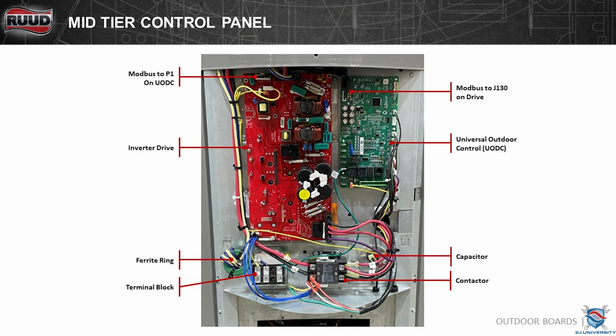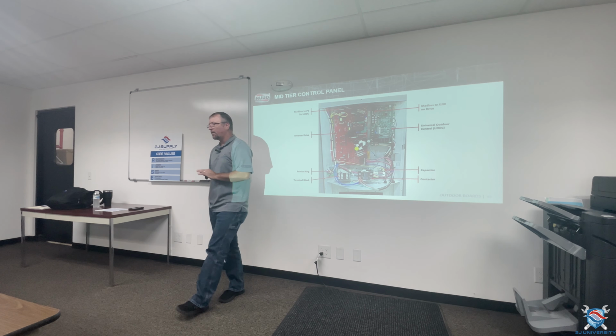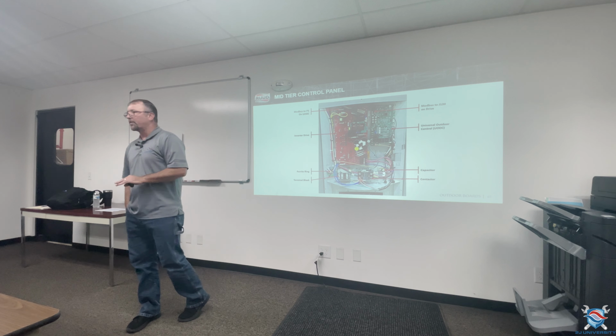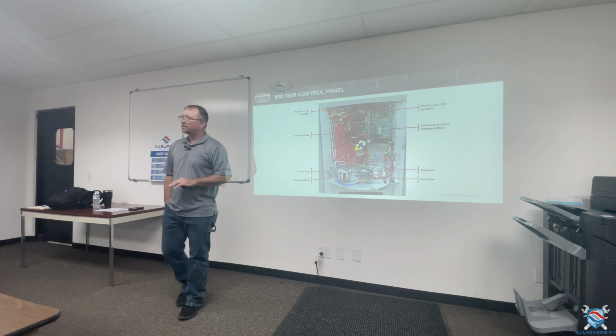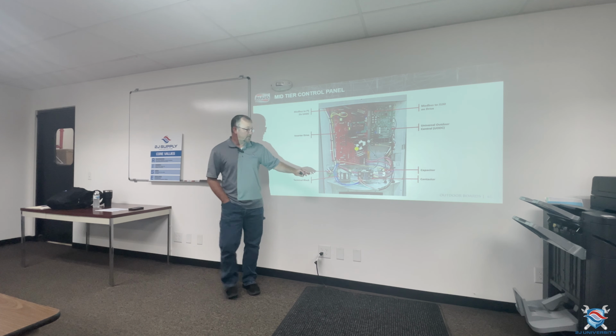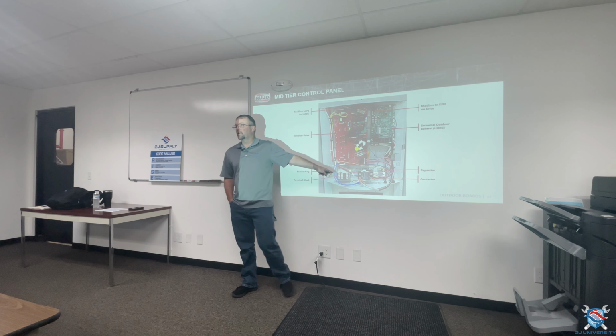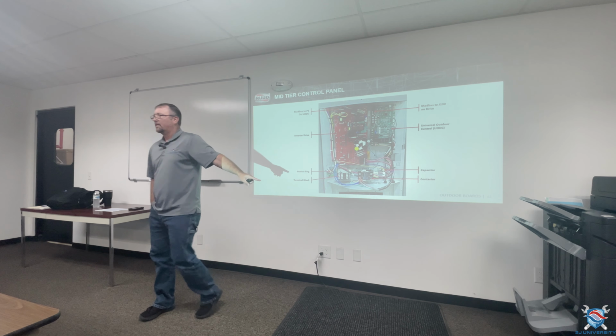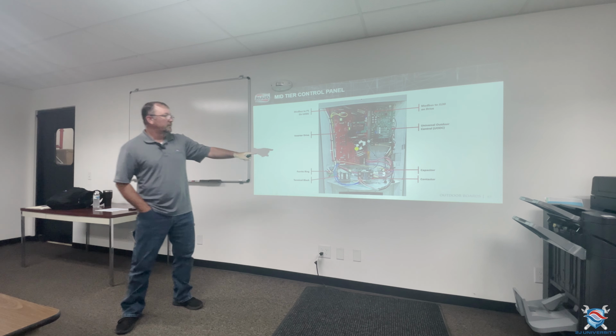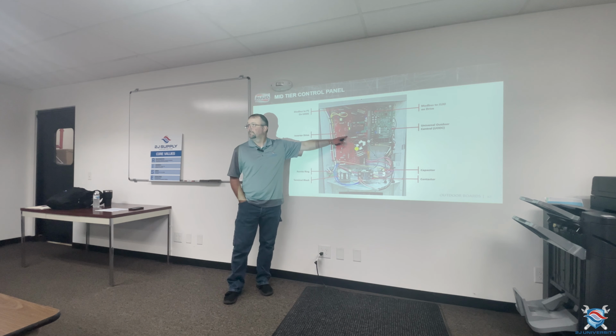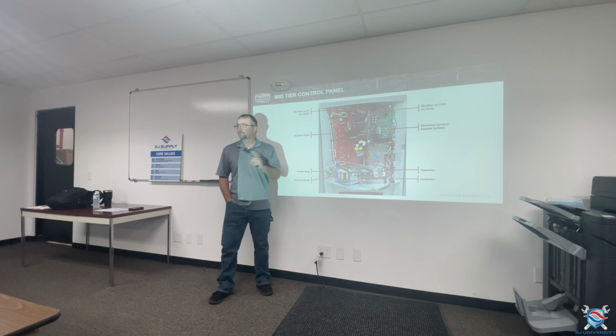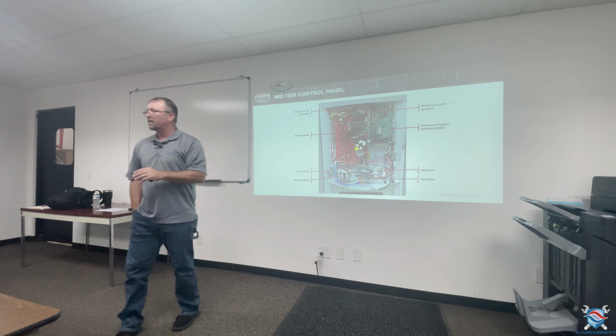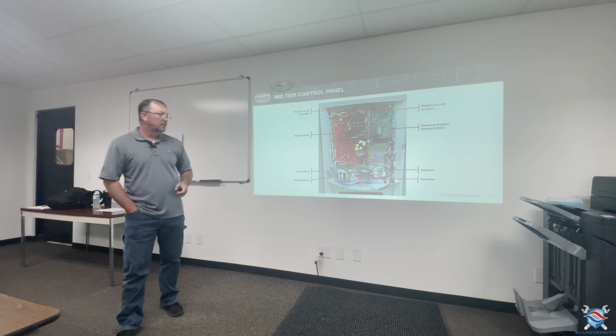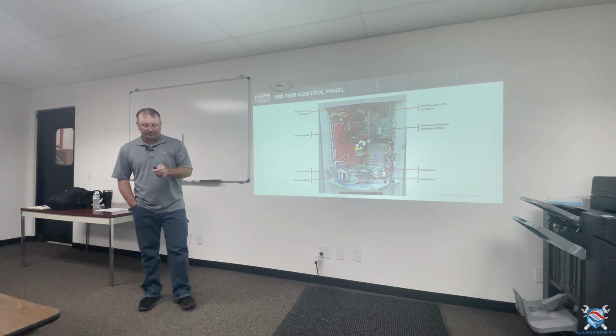On the contactor here, one thing I want to stress on any inverter system that has a contactor: never ever take this plate off and push that contactor in. If you do, you burnt that board, guaranteed. And I'll explain here in a minute a little bit why you never want to push that contactor in.